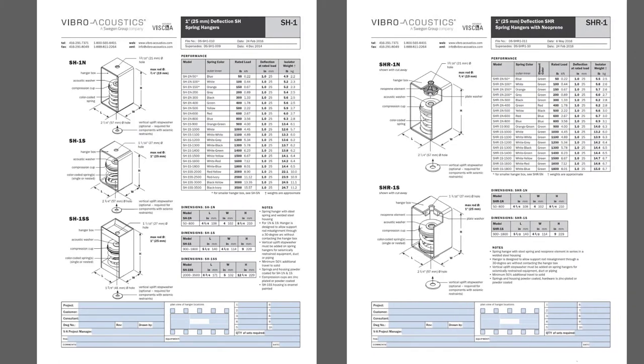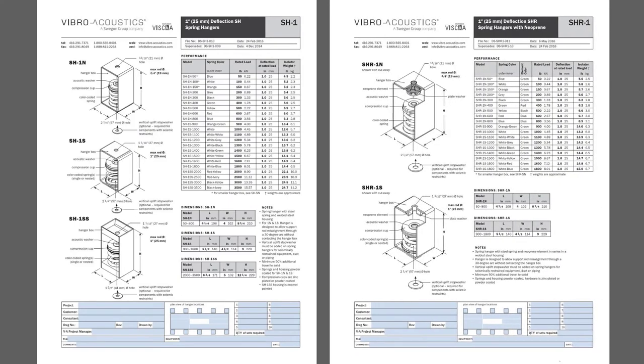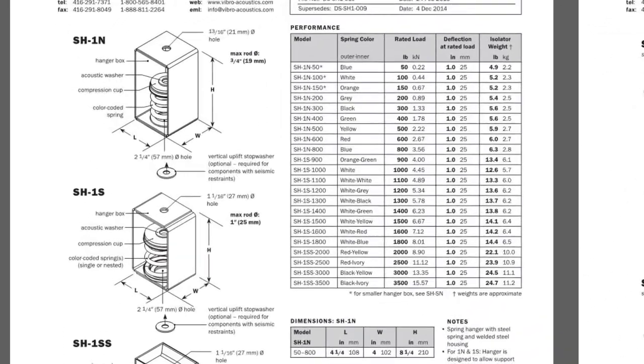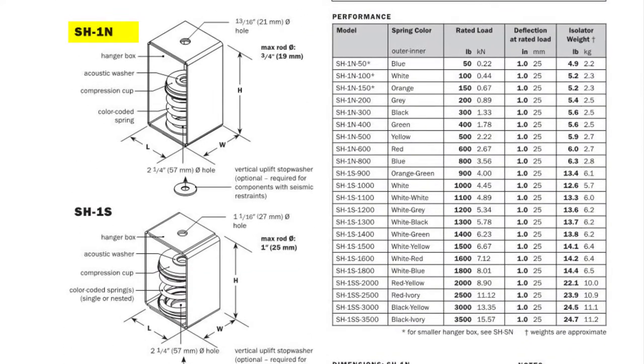Let's take a closer look at the first two versions the SH and SH-R. A common isolator used for supporting pipe is the SH-1N. It has a single color-coded spring in its housing. As an example an 8-inch pipe filled with water weighs about 50 pounds per foot and clevis supports are often spaced about 10 feet apart which means a single isolator may hold about 500 pounds. So SH-1N500 could be a good choice.